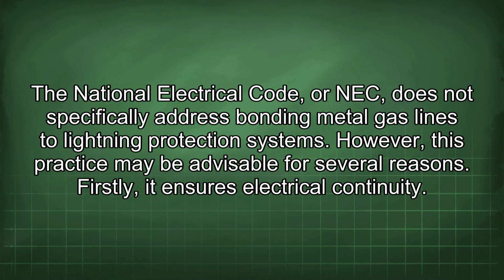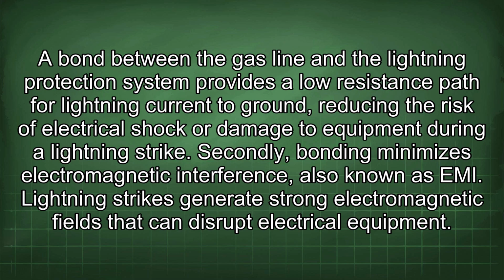The National Electrical Code, or NEC, does not specifically address bonding metal gas lines to lightning protection systems. However, this practice may be advisable for several reasons. Firstly, it ensures electrical continuity. A bond between the gas line and the lightning protection system provides a low resistance path for lightning current to ground, reducing the risk of electrical shock or damage to equipment during a lightning strike.